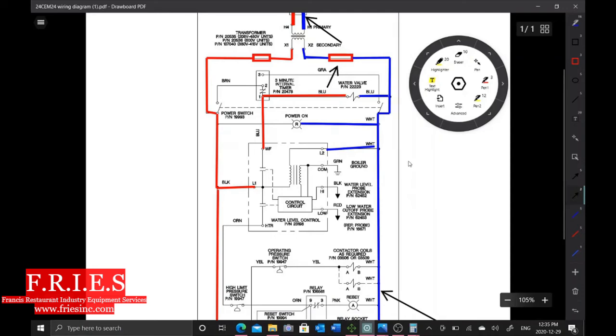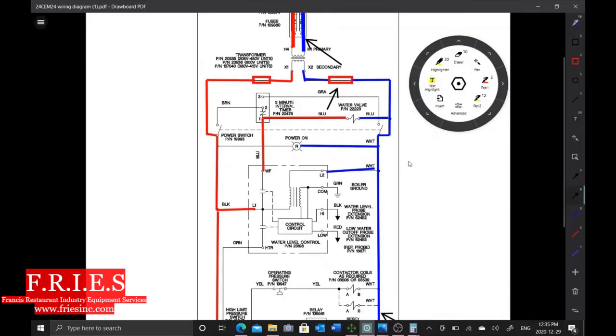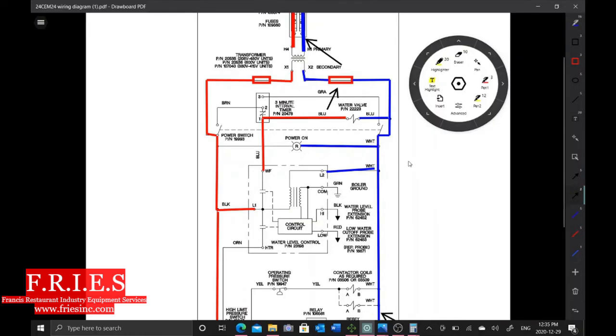Okay, so a couple hints that I was getting here that it was not a short—so I didn't look for dead shorts because I wasn't going to ohm everything out—was I was getting two seconds until it was blowing the fuse. It wasn't instantly. So that was telling me like something is seized or something's drawing lots of amps. My mind was stuck on that for the troubleshooting, but based on I had those fuses hooked up in line, it didn't matter to me how many attempts it took me because at this point I wasn't blowing the transformer.